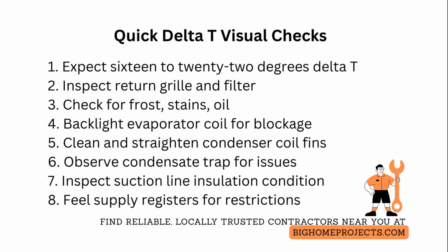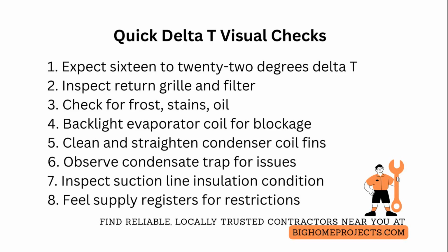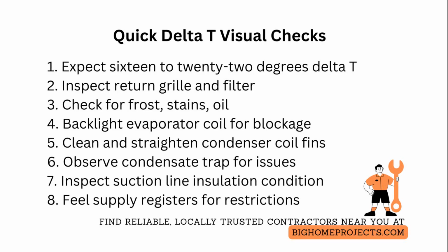Finally, scan supply registers with your hand for uneven throw or whistling that can indicate hidden duct restrictions, crushed flex, or disconnected takeoffs robbing airflow.